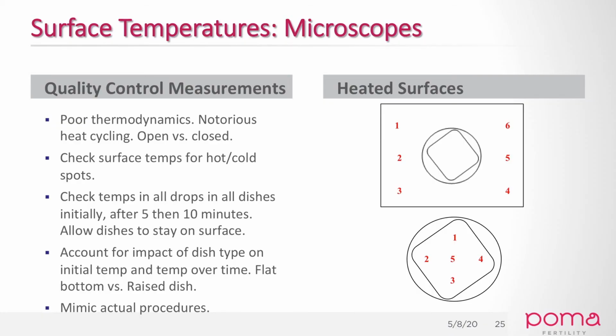And that's the same thing that we do with our microscopes. Again, I don't know when's the last time you calibrated your heated stage, but we all know that many of them have notoriously poor thermodynamics. They heat cycle and can make it worse if they're opened and closed. So again, you want to check for hot and cold areas. And again, when we're doing these things in our laboratory, we tend to mimic processes that we're going through in order to see what our temperatures are. So on the right here, our heated stage has the outer areas heated as well as the inside. So we check all the outer areas for hot and cold spots. And then the interior, we also check for hot and cold spots because we want to make sure that when we're doing ICSI or things like that, we're not actually getting too lethal with our temperatures. So you would be surprised what oil over the top does to your temperatures.